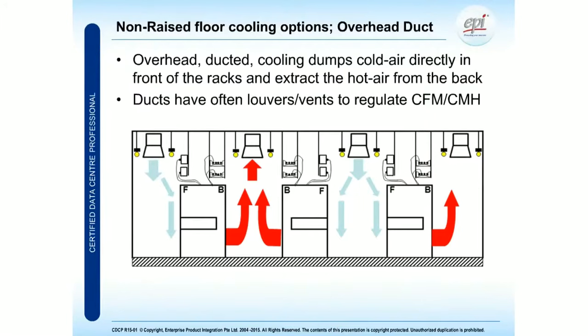For cooling we have many different types as well. In this case we have overhead duct systems where we can apply extra cooling capacity inside corridors or aisles. In this example, cold air is dropped from the ceiling and hot air is released through ducts hanging on the ceiling. There are many different systems available to get more cooling capacity.